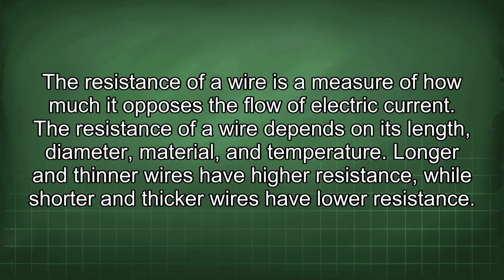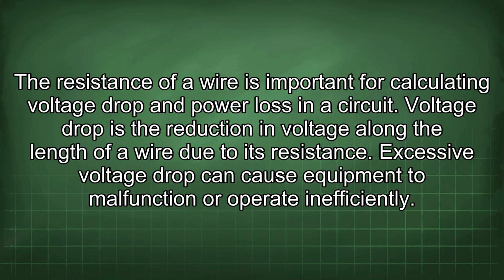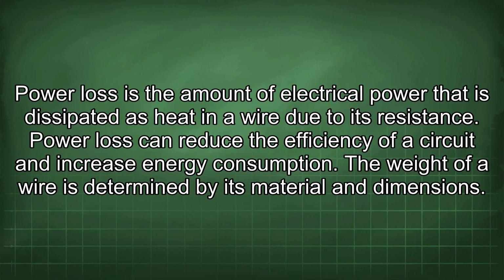Longer and thinner wires have higher resistance, while shorter and thicker wires have lower resistance. The resistance of a wire is important for calculating voltage drop and power loss in a circuit. Voltage drop is the reduction in voltage along the length of a wire due to its resistance. Excessive voltage drop can cause equipment to malfunction or operate inefficiently. Power loss is the amount of electrical power that is dissipated as heat in a wire due to its resistance. Power loss can reduce the efficiency of a circuit and increase energy consumption.